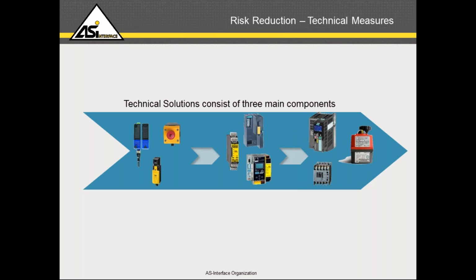And then reaction is the action of removing the hazardous motion or process, either by coming to a safe speed, managing a process variable like level, flow, temperature, etc., or by simply shutting down all or a portion of the motors associated with the machine.